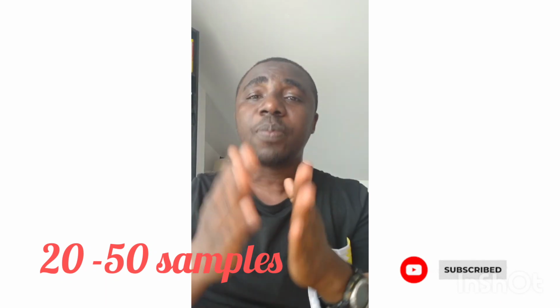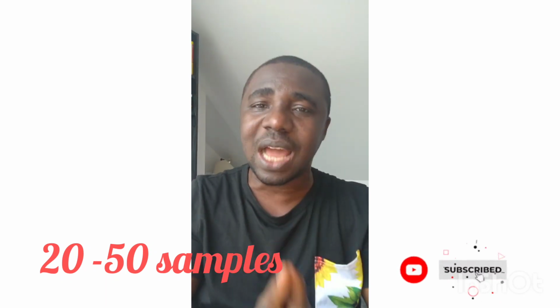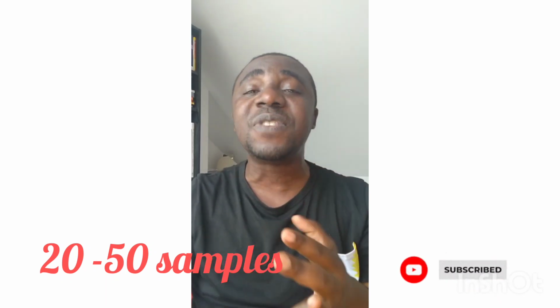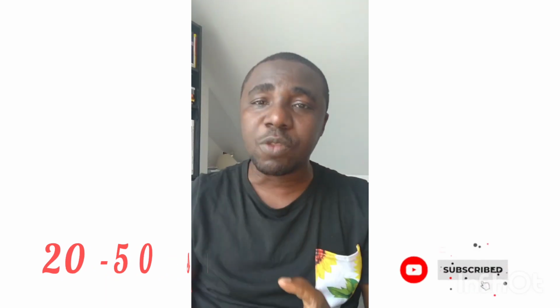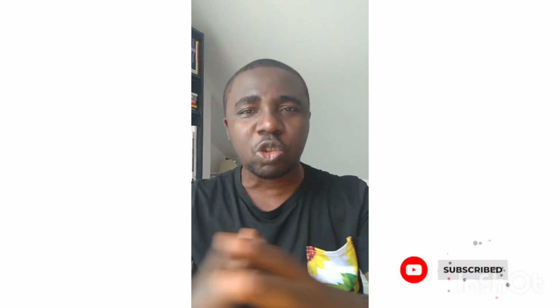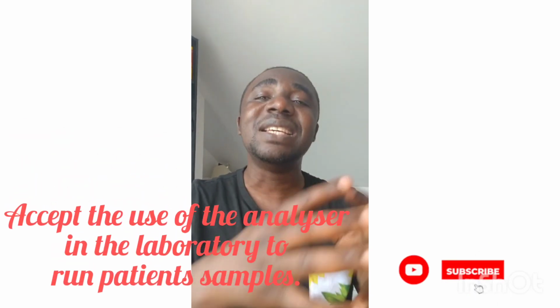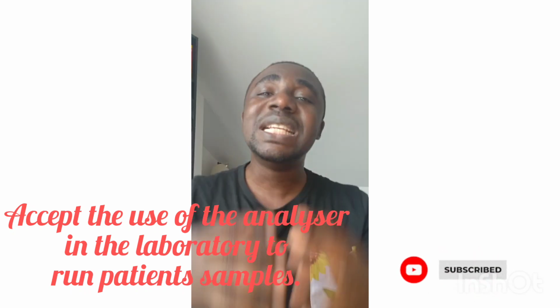You need to run 20 to 50 samples on that new analyzer, including both normal and abnormal samples, like I've said. Once the analyzer has given you reliable, true results, you can then accept that analyzer should be used to run patient samples. Once you accept it, that is then called analyzer validation, meaning you've validated that the analyzer is reliable, is good, and can then be used.